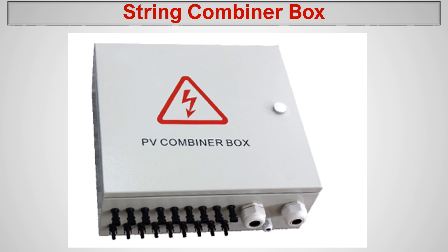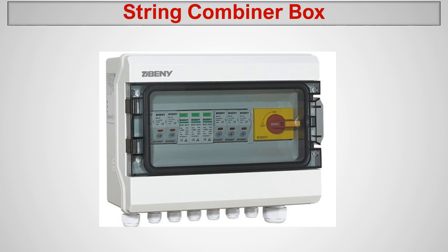What is happening in the combiner box, as I earlier said, involves two actions. First, combining all the strings into one output, because the inverter only wants one output — the inverter doesn't care how many panels there are, only how much current and voltage is coming in. Second, protecting the system. Each string needs protection individually, because sometimes due to faults some panels are damaged or producing over-current, so we handle each string separately.